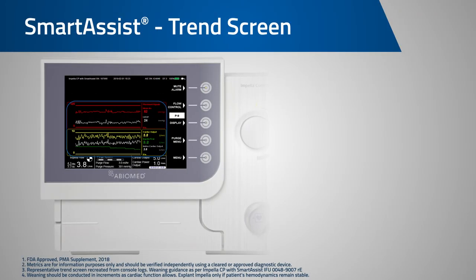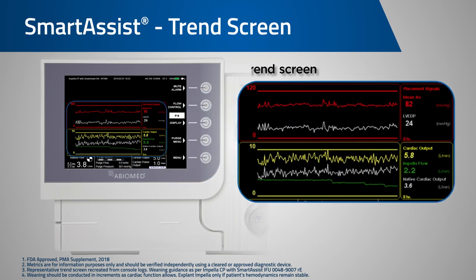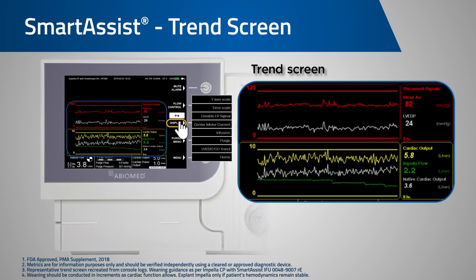These metrics are visualized using the new Trend Screen available with Smart Assist. The Trend Screen provides a reference to the relationship of individual metrics over time. It can be beneficial in helping inform decisions especially during weaning or ramp studies. To access the Trend Screen, you are going to use the soft keys to select display and then the LVEDP cardiac output trend.